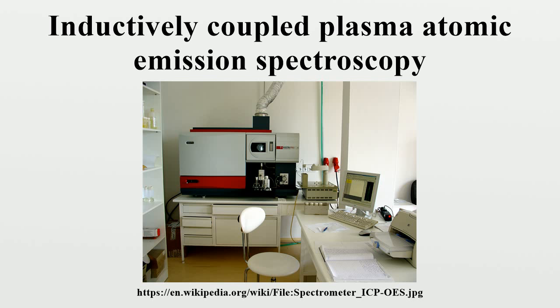The ICP-AES is composed of two parts: the ICP and the optical spectrometer. The ICP torch consists of three concentric quartz glass tubes. The output or work coil of the radio frequency generator surrounds part of this quartz torch. Argon gas is typically used to create the plasma.